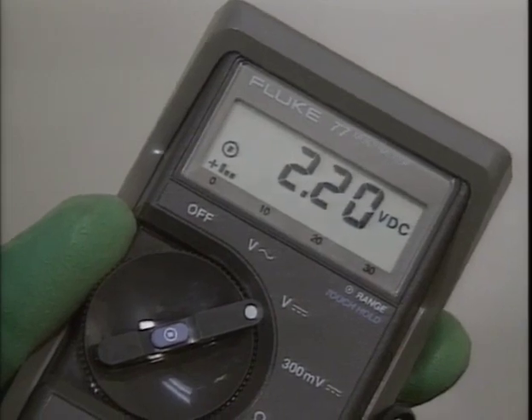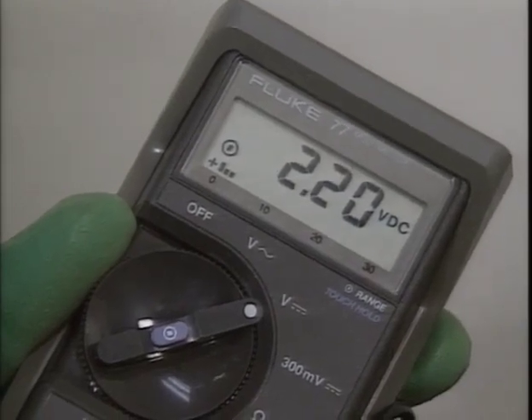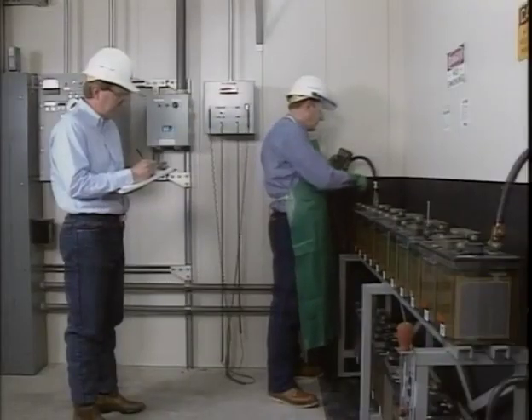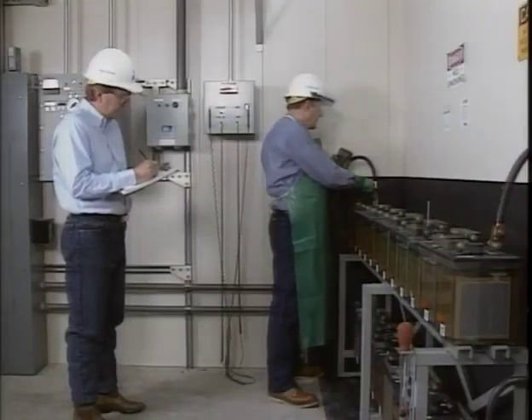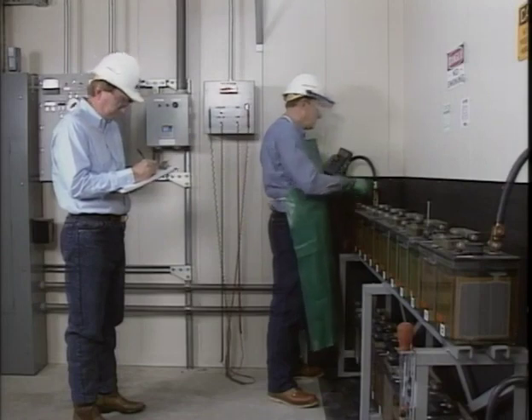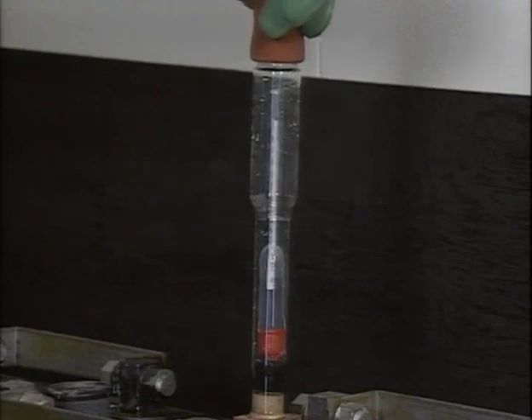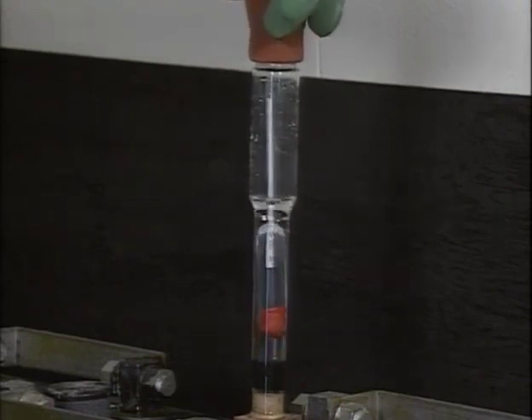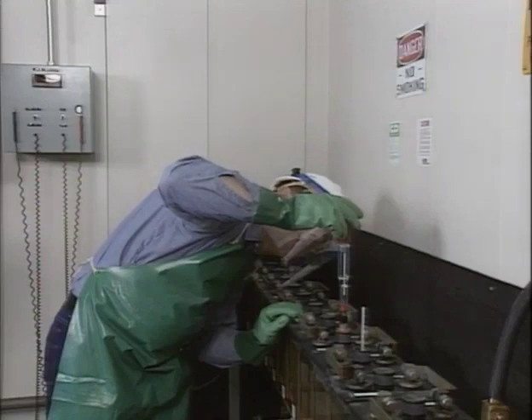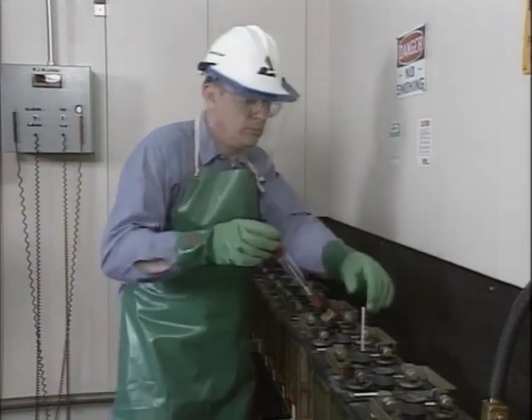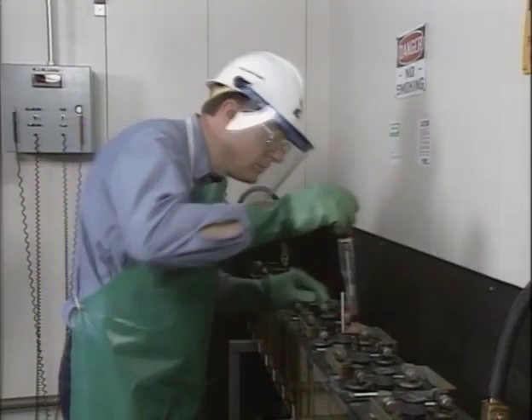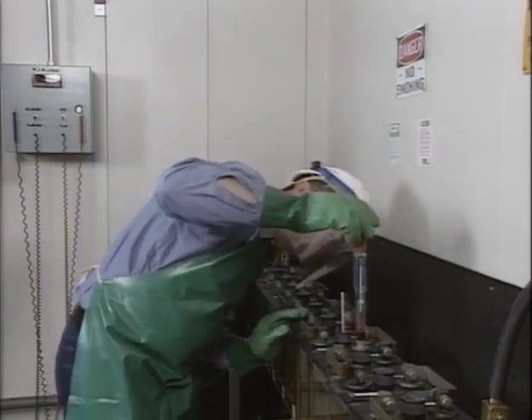Voltage testing was shown to help identify cells that aren't being adequately charged. This part of the program also showed a number of possible causes of low voltages and high resistances. Voltage and resistance tests are two of several tests that are helpful in checking the condition of substation batteries. Another useful test is a specific gravity test. Specific gravity testing will be described in the next part of this program. But before continuing, stop the tape and read the voltage and resistance testing portion of your text and answer the questions provided.